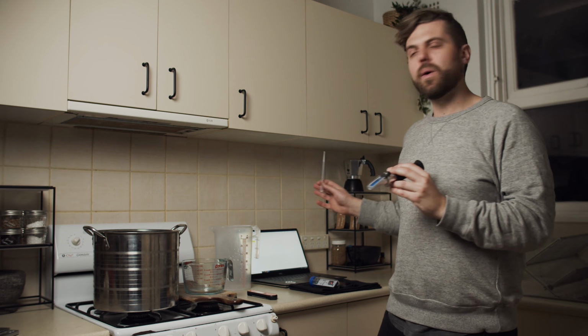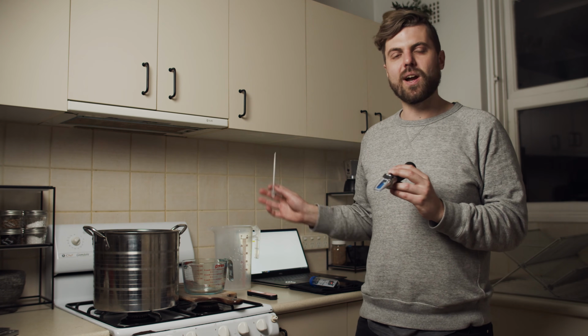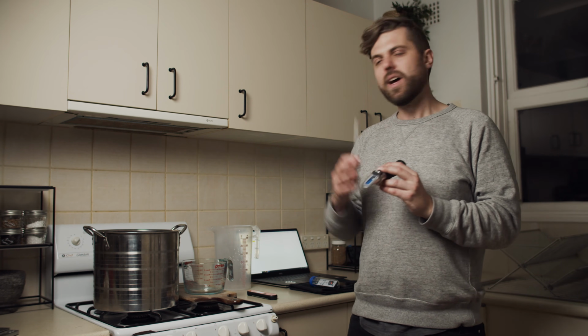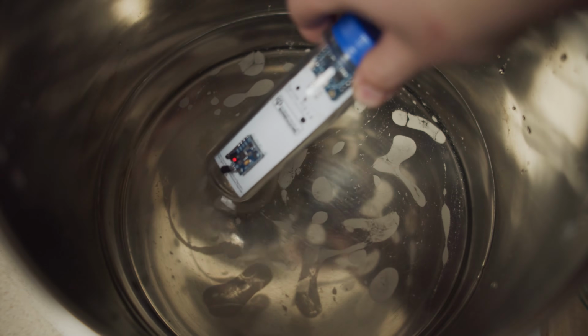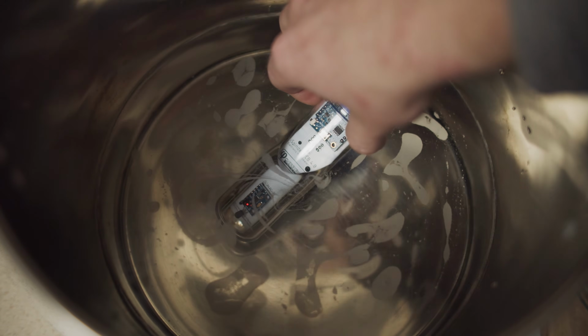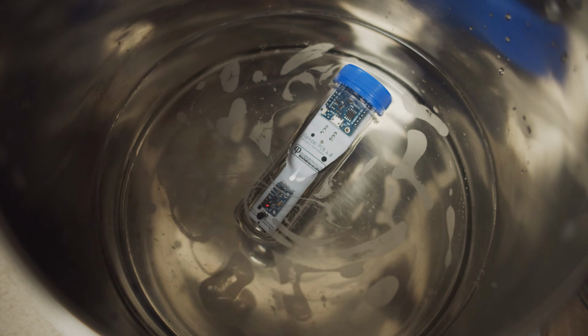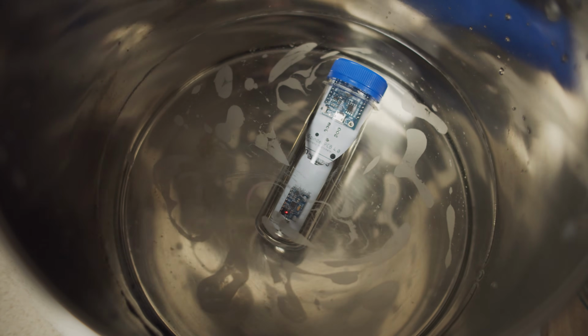Don't worry if it's a point or two below or above, that's fine. We're going to enter the exact value anyway into the graph, so that's what it's going to calibrate to. As long as you're doing roughly every 10 points, everything's all good. So next thing to do, we're gonna add 1.082 there. We're gonna record the tilt value with the iSpindel in there, and then we'll move on. When you're taking your readings, just make sure the iSpindel's not touching the bottom of the vessels or the sides. It may just end up in a false reading.